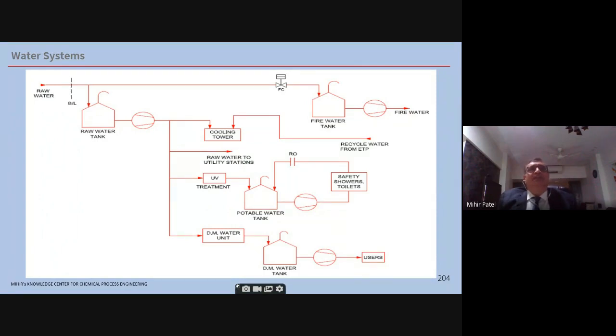Raw water can go to utility stations for floor washing, etc. It can go to the potable water system where you have a UV treatment, ultraviolet treatment. Alternatively, you can also dose sodium hypochlorite, NaOCl, which is also good for killing the bacteria so that the potable water doesn't have fungus or bacteria in it. This potable water is used for two purposes. First is safety showers, second is the toilets in the buildings. So it is normally a closed circulation because safety showers is a safety device. It has to be in operation 24/7. So this pump always has emergency power also.